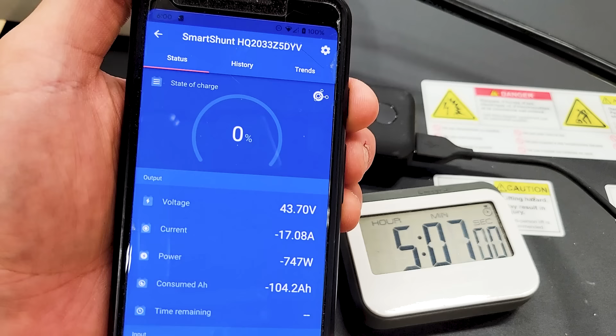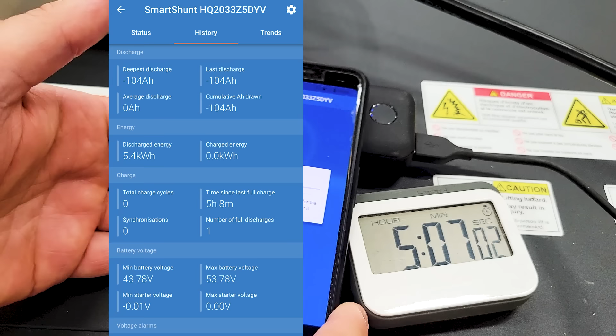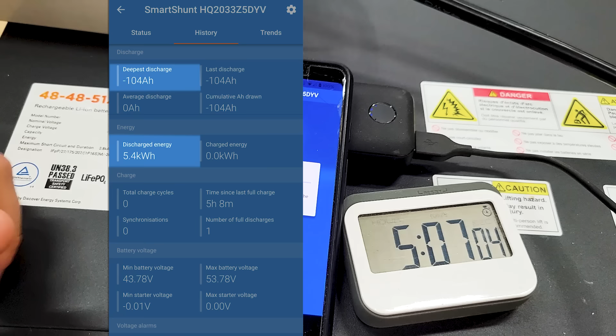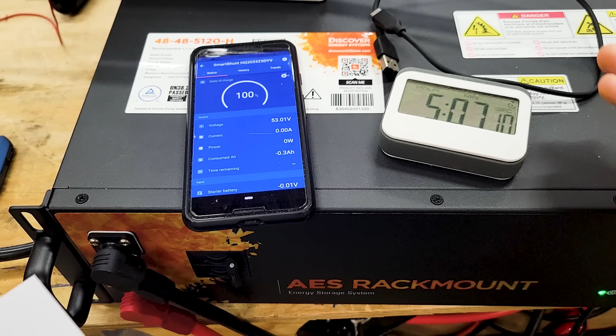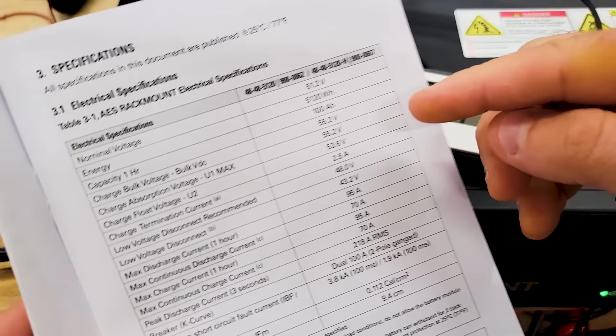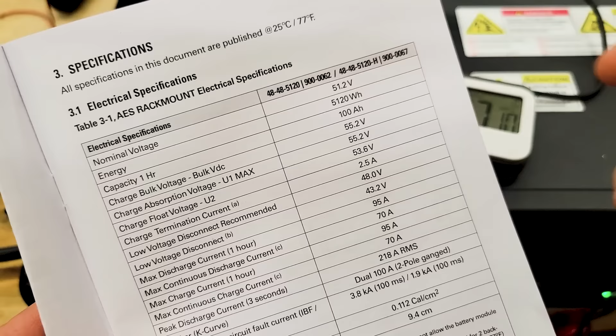There we go. And it just shut off, went to 0, disconnected. That's excellent. Really good test here. So far, this battery has been working really well. We've tested our continuous discharge at 95 amps for 1 hour. We've also tested our capacity at 5.12 kilowatt hours. So both of those, it passed.